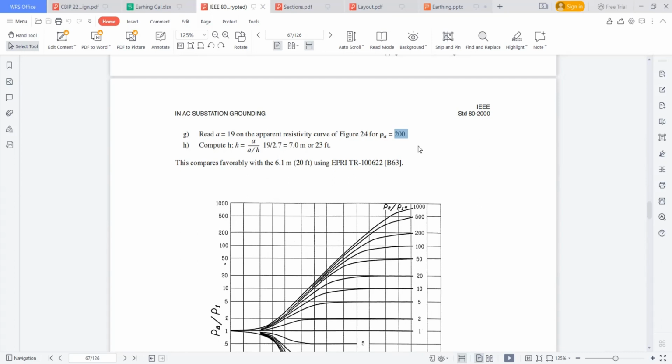Is there a product that you put in the soil to decrease the resistivity? Ashwin, I didn't get your point. Please repeat the question. Do you put some product in that part of the soil just to get a good resistivity? Some chemicals? Yes, that is the other way. Yes, we have different types of products, like a gem compound, or let's say bentonite powder is one product.